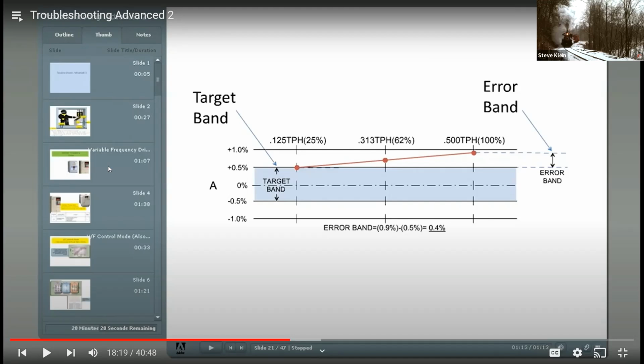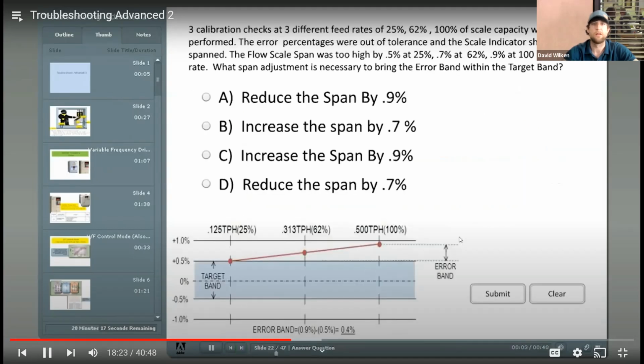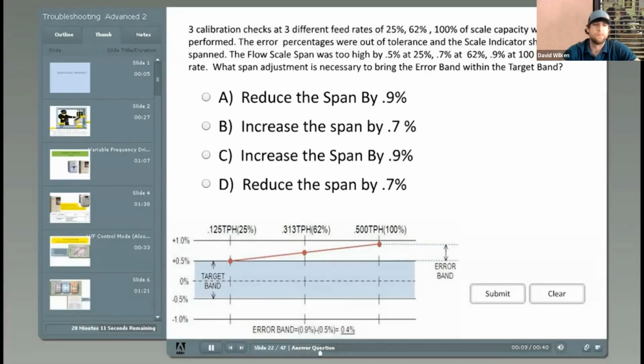You want to skate on ahead then, Dave? Yeah, there's a question right here. Calibration checks at 3 different feed rates of 25%, 62%, and 100% of scale capacity were performed. The error percentages were out of tolerance, and the scale indicator should be respanned. The flow scale span was too high by 0.5% at 25%, 0.7% at 62%, and 0.9% at 100% flow rate. What span adjustment is necessary to bring the error band within the target band?